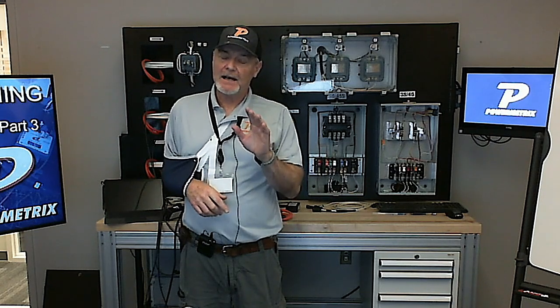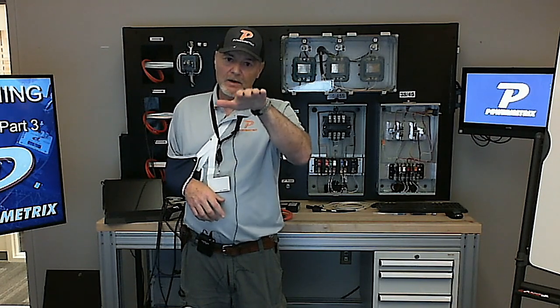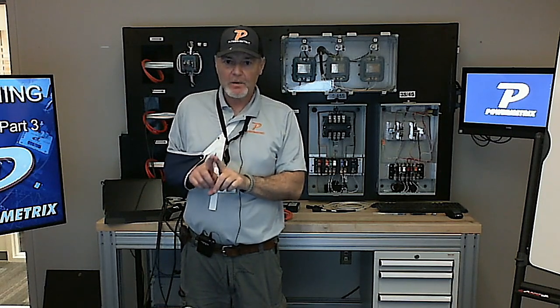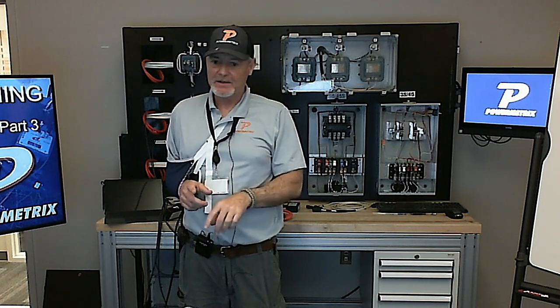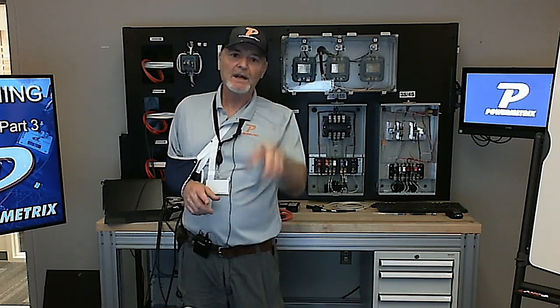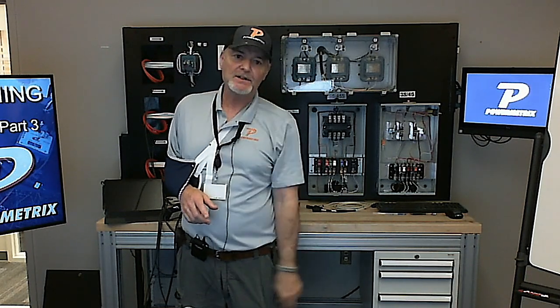That's why that adapter they've got is so great, because you can slide right over the top of the CT and grab them where they're closest together, which is right at the CT. As soon as they start getting away from that CT, the 2 conductors spread apart there. So the closer you can get to it, the better chance you have of getting around both of them at the same time.